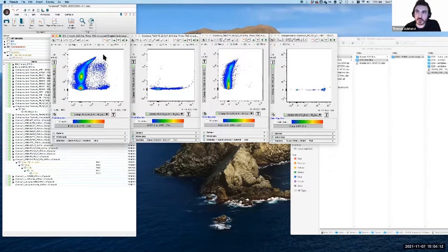So I really need to have checked the actual combination of the offending fluorophore, the target, and the non-target detector to see this undercompensation problem. These are much harder to spot because you really have to go and check each of these combinations. But essentially the same rules apply. We've identified and flagged it, and now we want to see whether this is something genuine or something which is not real, which we need to correct. So we have the same sort of deal.